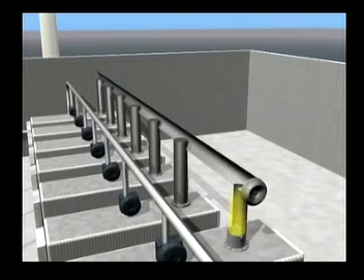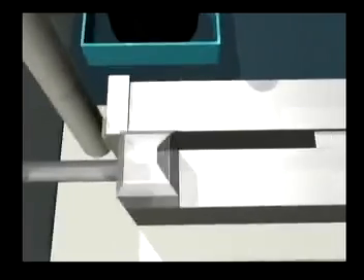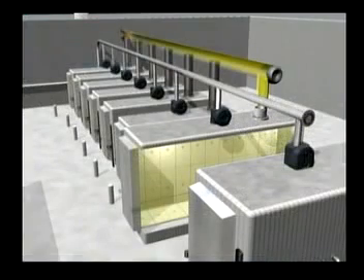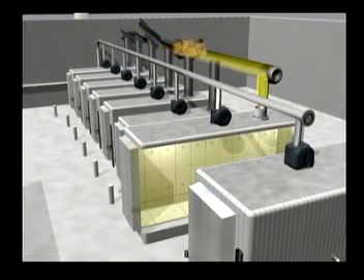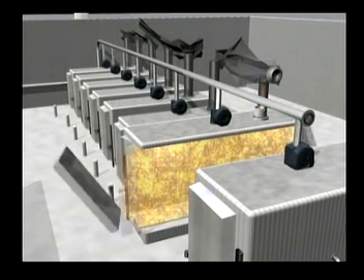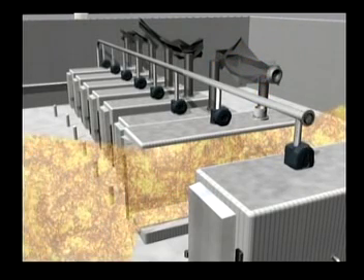This drew a large amount of ethylene oxide from the chamber through the back vent to the open flames in the oxidizer. The explosive gas ignited. A flame front traveled back through the ducting, into the sterilization chamber, igniting the remaining ethylene oxide and causing a powerful explosion.